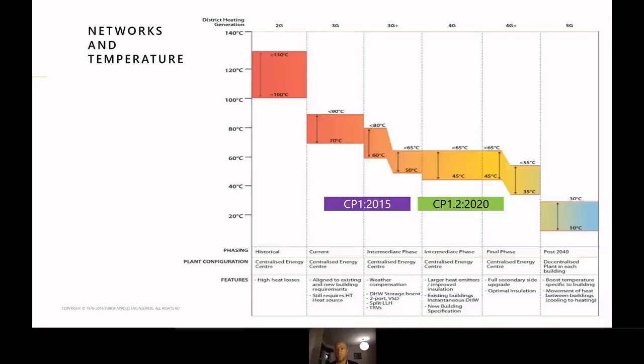Big changes being around diversity: much stronger guidance on diversity for domestic hot water, also diversity for space heating, as well as stronger guidance on the temperatures required for domestic hot water, which is absolutely essential to nail down to allow us to deliver the maximised amount of low carbon heat from heat pumps. But CP1.2 doesn't yet stretch into the 5th generation, so it's a little bit unguided at the moment from that perspective. I think a lot of people are working on it.